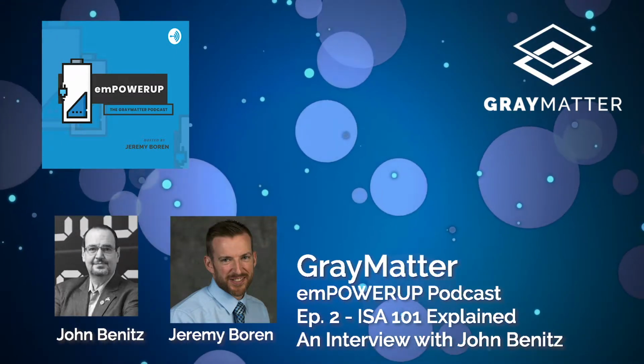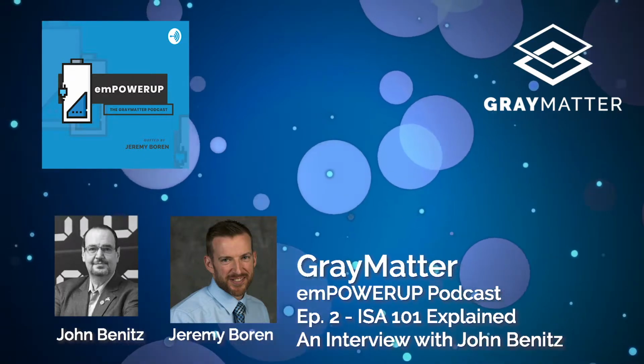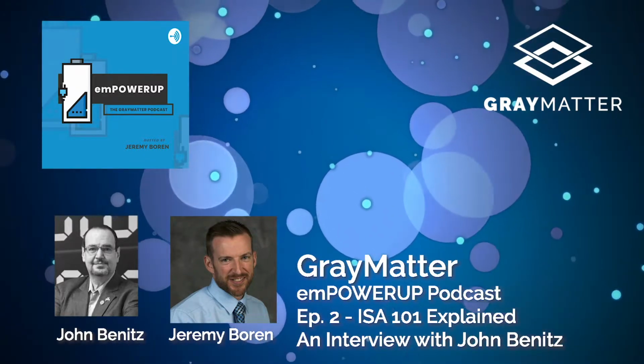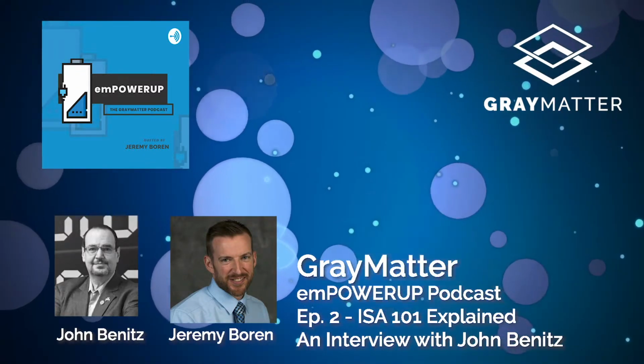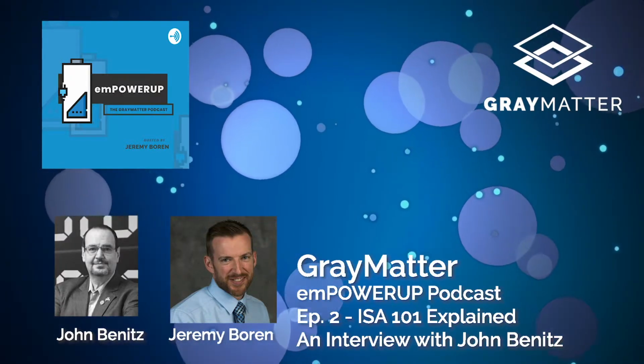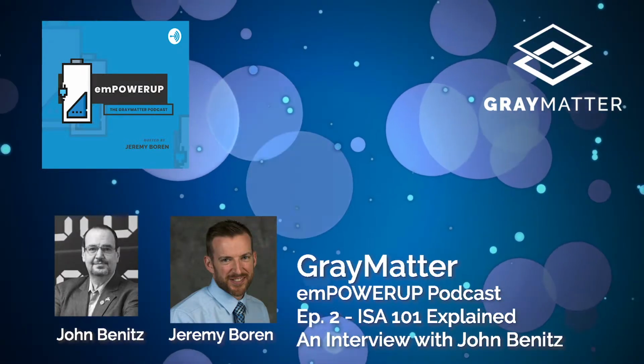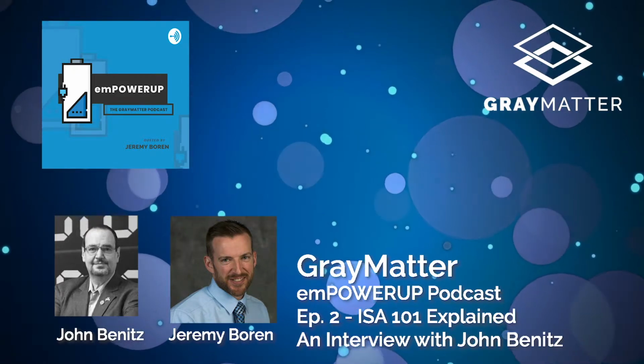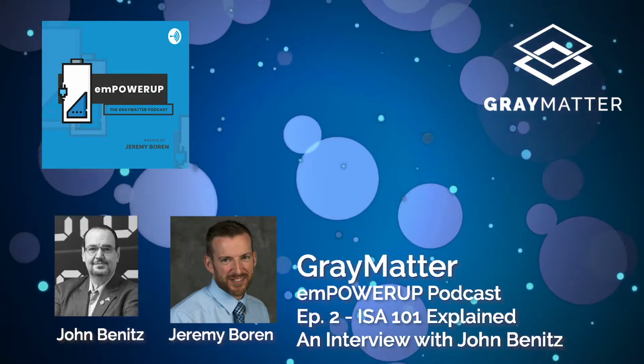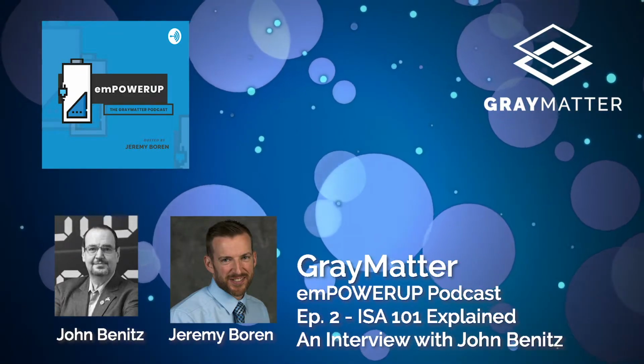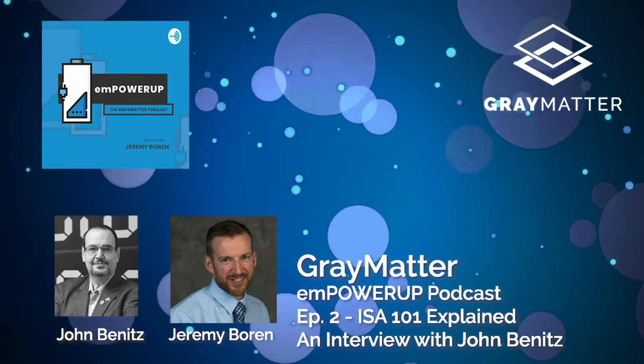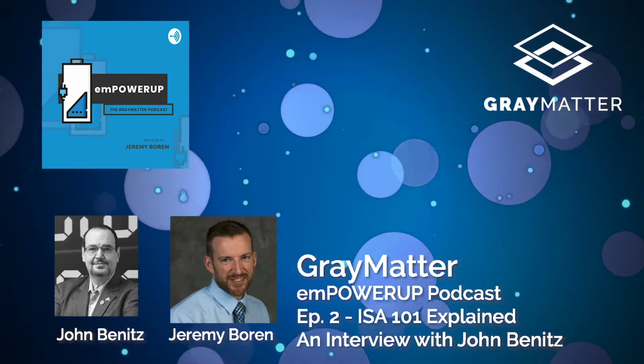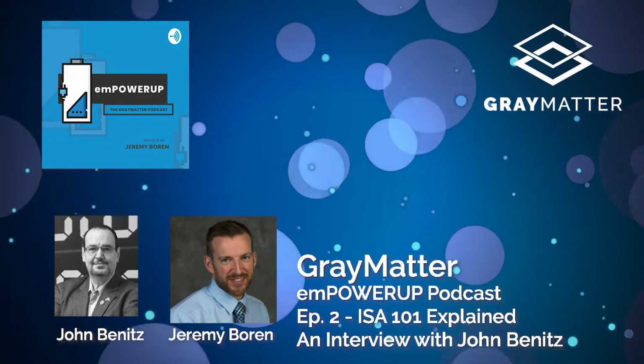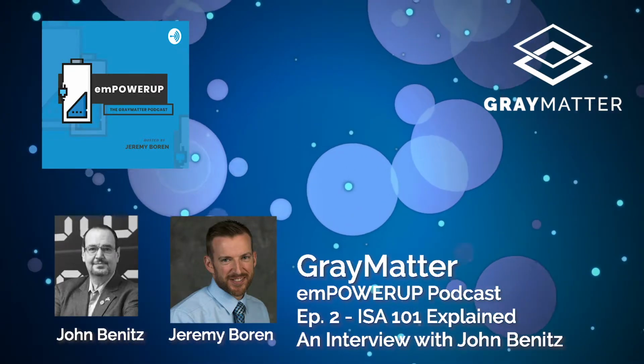So that's why we discussed using grayscale. Also, if you look at a screen that has a lot of detail on it and things are grayscaled, so white is indicating running or some action is energized, and gray means it's there but it's not energized, and something turns red or something turns yellow, it's really going to draw your attention to that item.